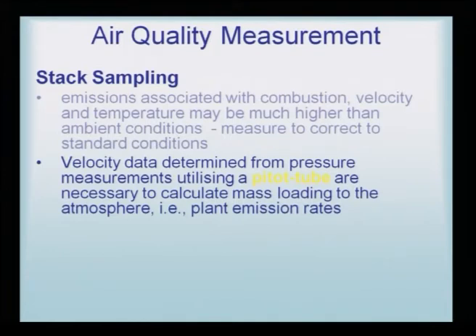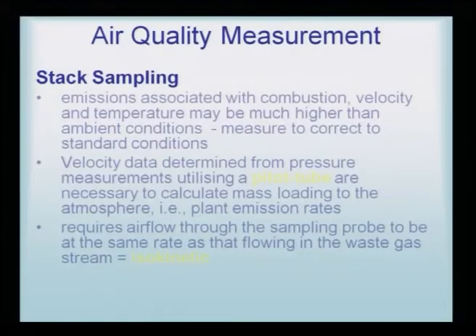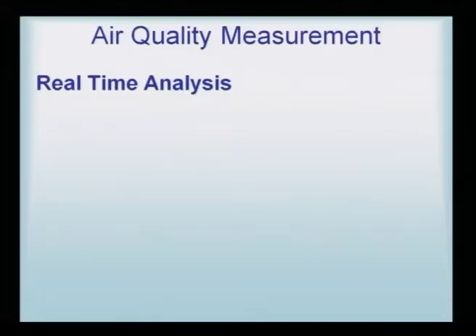Velocity data determined from pressure measurements utilizing a pitot tube are necessary to calculate mass loading to the atmosphere. That means plant emission rate. If a steel plant or a blast furnace has emissions, then the flow rate and the velocity data should be determined very precisely. This requires airflow through the sampling probe to be at the same rate as that flowing in the waste gas stream, so it should be isokinetic. If the speeds are different, then some things would go unanalyzed.